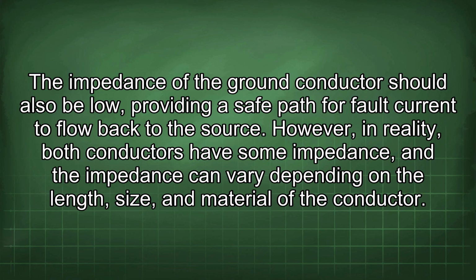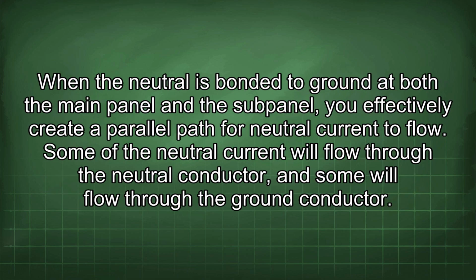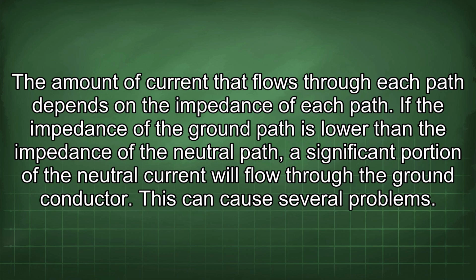However, in reality, both conductors have some impedance, and the impedance can vary depending on the length, size, and material of the conductor. When the neutral is bonded to ground at both the main panel and the subpanel, you effectively create a parallel path for neutral current to flow. Some of the neutral current will flow through the neutral conductor, and some will flow through the ground conductor. The amount of current that flows through each path depends on the impedance of each path. If the impedance of the ground path is lower than the impedance of the neutral path, a significant portion of the neutral current will flow through the ground conductor. This can cause several problems.